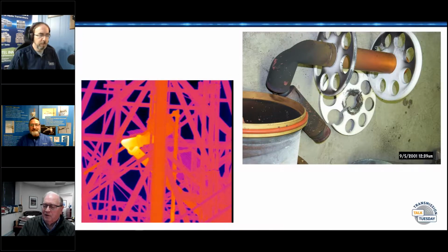And that is a huge point - establish your benchmark. What's normal? Then go back a month or two later and scan things again. Is it different? And while you're there with your thermal camera, look at your electrical panel, your breakers - what's normal for that? Beyond that, it's critical, if you're using one of these little thermal imaging cameras, take note of your contrast settings, because I can make that deviation represent 10 degrees, or I can make it represent 100 degrees, depending on how I set the contrast in the software on the camera. That's a whole other seminar on how to do thermal imaging. So record your measuring settings, your measuring device settings, as well as what you're actually measuring, because that way you'll be able to repeat your benchmark - an experiment you can't repeat is not really an experiment.